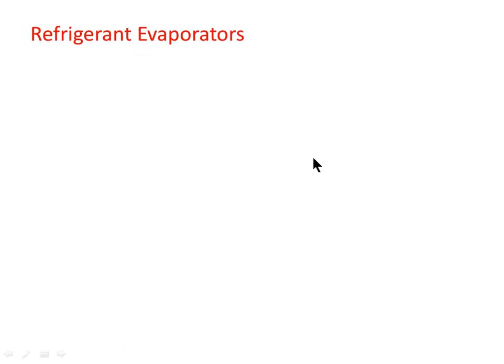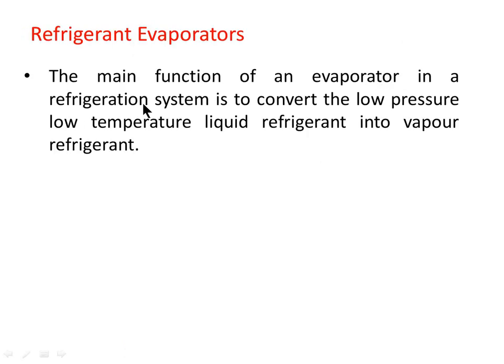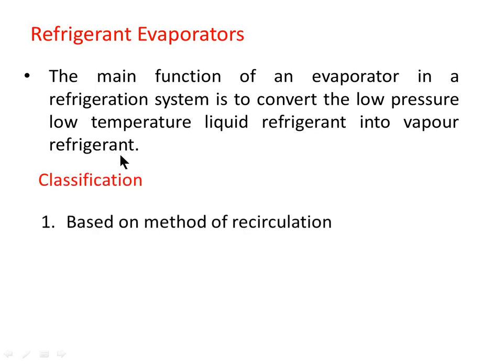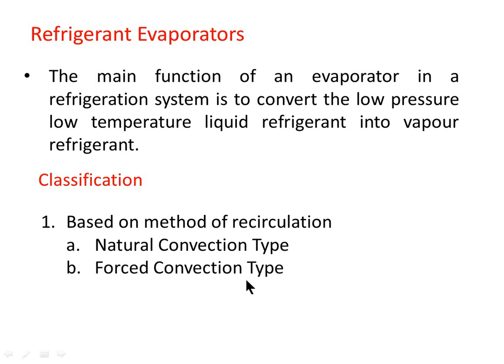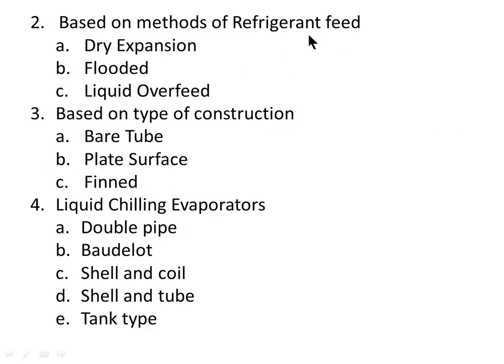Next are refrigerant evaporators. The main function of an evaporator in a refrigeration system is to convert low pressure, low temperature liquid refrigerant into vapor refrigerant. Evaporators are classified based on method of recirculation into natural convection and forced convection types; based on method of refrigerant feed into dry expansion, flooded, and liquid overfeed types; and based on construction into bare tube, plate surface, or finned types. Liquid chilling evaporators include double pipe, Baudelot, shell and coil, shell and tube, and tank type evaporators.